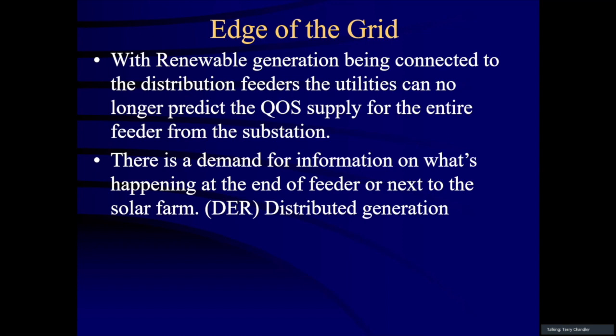That's been a big drive for getting information on what's happening at the end of the feeder or next to the solar farm. What is now named, just for buzzwords, is DER, or distributed generation. Interestingly, in Thailand we were pioneering: the utility, with a little help from us, now has a regulation that requires any new solar farm that generates more than 100 kilowatts to have a power quality meter attached to the output that the utility can access.